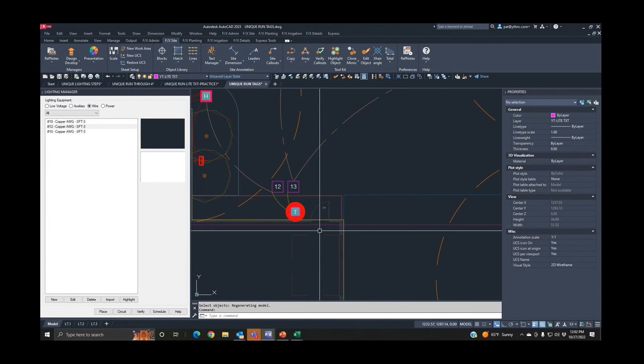Let's jump out to Excel and see what's really going on. The way we calculate this voltage drop using VA and taps — because we're increasing our tap, our actual wattage went up. So we're showing a total actual wattage of 166, and we're trying to squeeze that into a 150 watt transformer. That's why LandFX is saying, no, you can't do this.